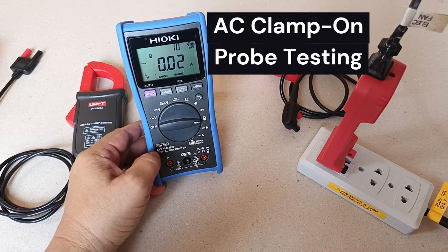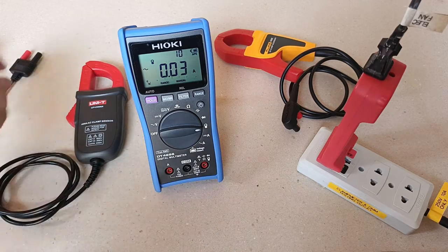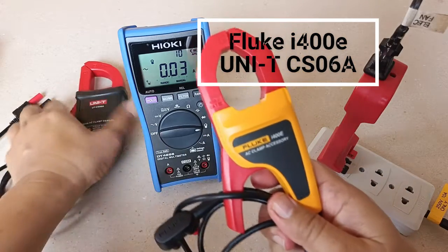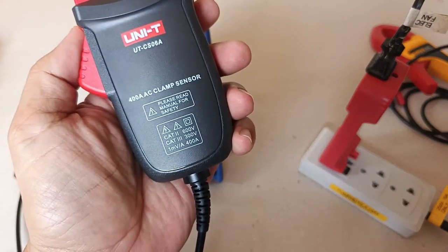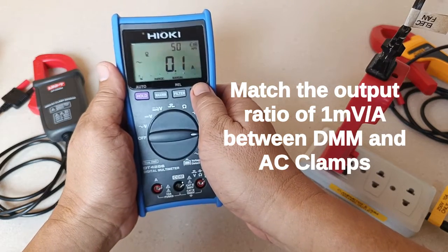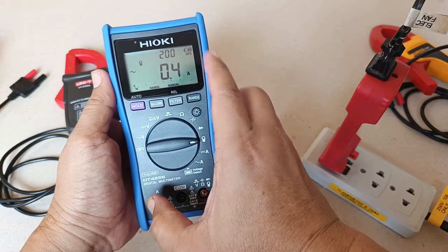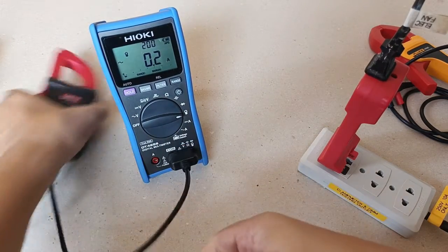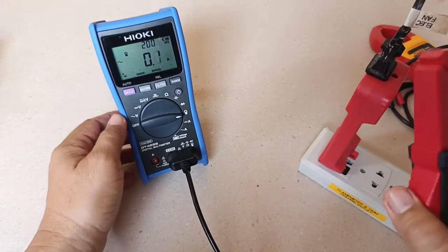Another notable feature of the DT4256 is its AC clamp-on probe slot. Hioki manufactures its own AC clamp-on probe accessory, but it is also compatible with the Fluke i400D and the lower-cost UNI-T UT-CS06A, both of which have a similar output ratio of 1 millivolt per ampere. All you have to do is change the range of the DT4256 to match that 1 mV/A output ratio, which corresponds to the 200-ampere range. Although you won't be able to utilize the full 400-ampere capacity of these clamp accessories, if you only need to measure up to 200 amperes this is perfectly fine.